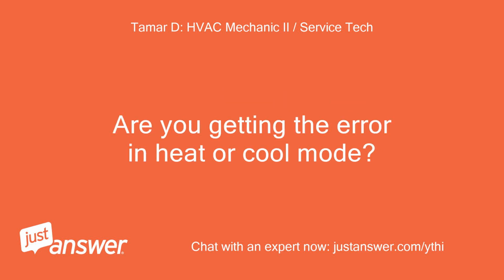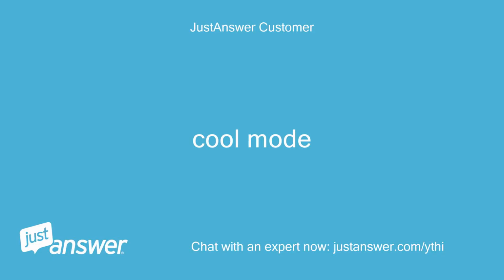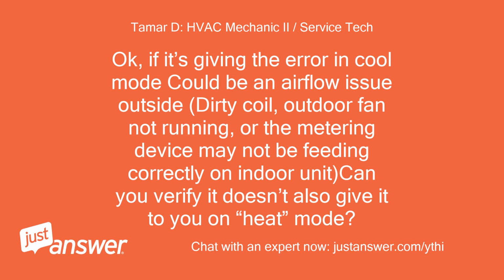Are you getting the error in heat or cool mode? Cool mode. Okay, if it's giving the error in cool mode, could be an airflow issue outside, dirty coil, outdoor fan not running, or the metering device may not be feeding correctly on indoor unit. Can you verify it doesn't also give it to you on heat mode?